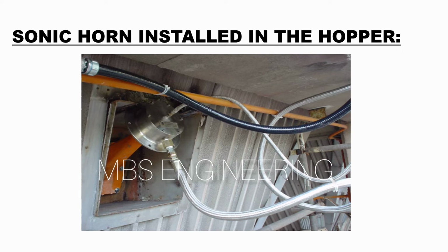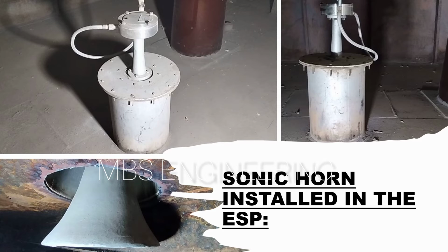Please refer to the picture. The sonic horn is installed in the hopper. In a bag filter hopper, it is used to prevent dust buildup, eliminate bridging, and sidewall dust buildup, and prevent hopper blocking. Please refer to the picture of the sonic horn installed in the electrostatic precipitator ESP. In ESP, it is used to improve the efficiency of the rapping system and increase collection efficiency. It is used to remove the dust built into the collecting plates and discharge electrodes. In ESP, it is used to prevent dust buildup and enhance the uniform distribution of gas flow. The ESP and bag filter hopper is used to prevent dust buildup, eliminate bridging, and sidewall dust buildup, and prevent hopper blocking.